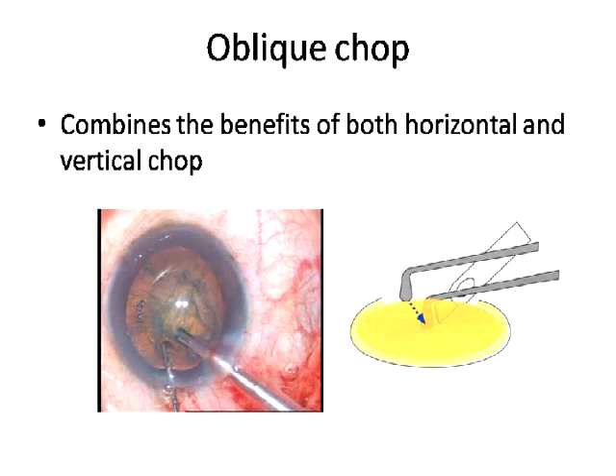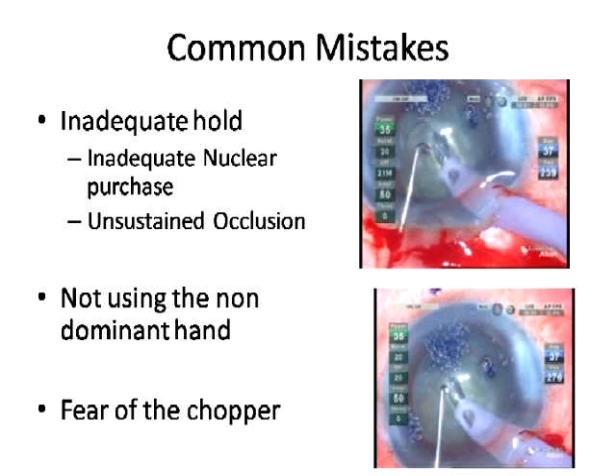Common mistakes: inadequate hold is the most common. The probe is not embedded deep enough into the nucleus — though there may be a trench, the probe itself is not completely impaled in the substance of the nucleus. The other issue is unsustained occlusion — the Phaco probe is deep enough, but the surgeon keeps exiting to foot pedal one. You'll see occlusion achieved multiple times but not maintained long enough to execute a chop.